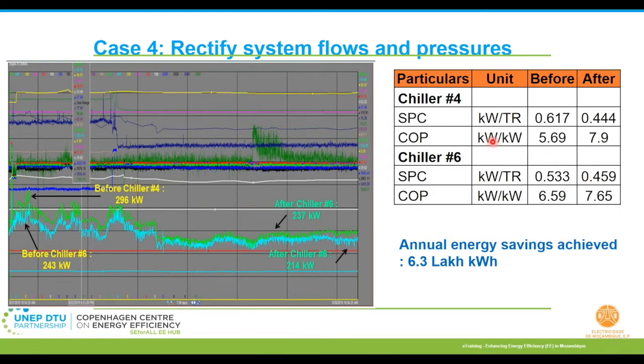Looking at the COP or specific power consumption values before and after, the system has also improved. On an annual basis, they were able to achieve savings of about 6.3 lakh units, and this is basically with no investment. It is just about rectifying and improving your operational efficiencies, not completely relying on your control systems, but also having some logic in place to identify where there are any flaws or not.